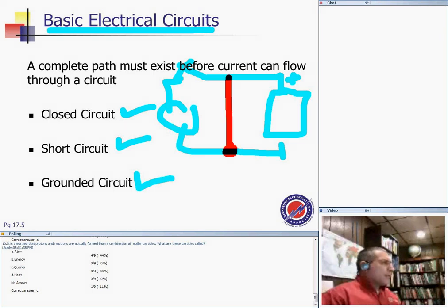For the grounded circuit, guys, you can grab another conductor and ground it, or you take one conductor in an alternating system and ground it, intentionally or unintentionally. That gives you a closed circuit, a short circuit, or a ground fault, a grounded circuit. I don't want to dwell on the grounded conductor because sometimes we ground it intentionally, and sometimes it's a ground fault.